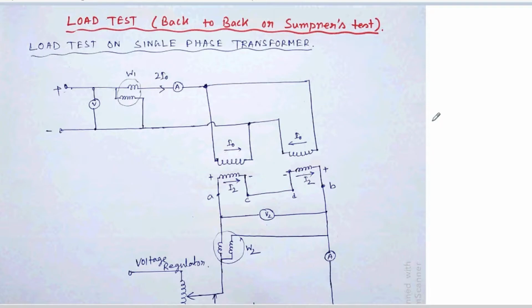we need a suitable load that is capable of absorbing full load power, and which is not easily available. So for a large transformer, this load test is very useful to determine the maximum temperature rise and also the efficiency, though the efficiency can be determined by using the open circuit and short circuit tests. And here the load test is done for a single phase transformer.